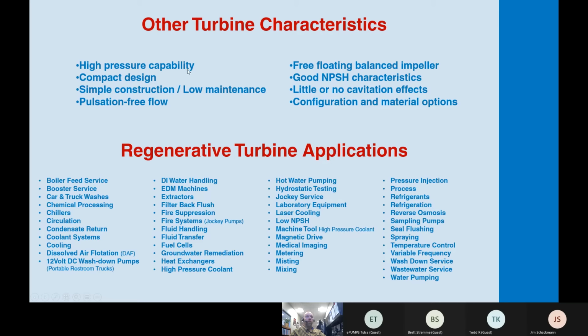But some of the other characteristics besides the high pressure are that they are a compact design. When you need to increase pressure with a centrifugal pump, you need to use a multi-stage centrifugal. With a regen turbine, all the pressure is built into a single or up to 4 or 5 stages, which would normally take 10 or more stages of a centrifugal pump. So you're going to go from a 10-stage centrifugal pump to a single stage regen turbine pump to achieve the same pressure in many instances. And because of this, you'll have simple construction. So you'll have 3 parts instead of multiple stages.